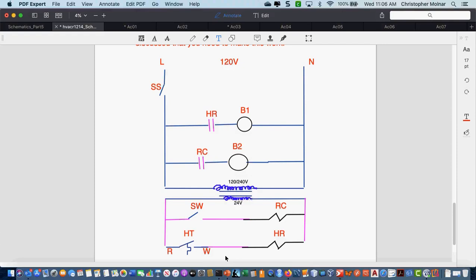What is the sequence of operation on this diagram? Line voltage is given to the transformer, which then, you close the switch powering your coils, your RC. RC powers bulb 2, and once your heating thermostat satisfies, your HR powers bulb 1. Okay, you're very close, but does the heating thermostat satisfy or does the heating thermostat call? Calls, sorry. Okay, yeah, when you're talking about a thermostat, satisfies puts it back in the open position. Calls keeps it closed, it's calling for heat. Okay, yeah, that was exactly right.